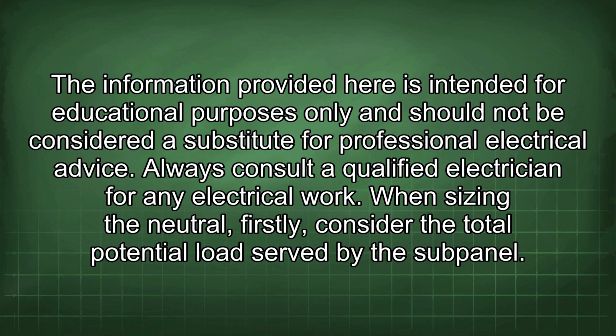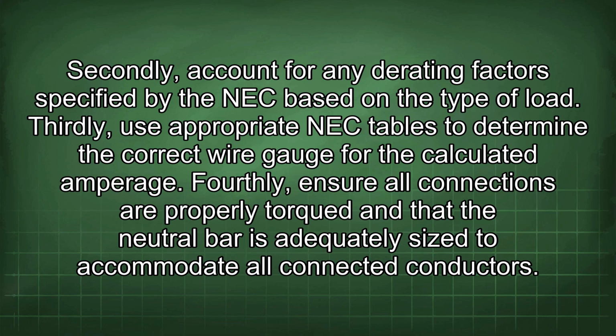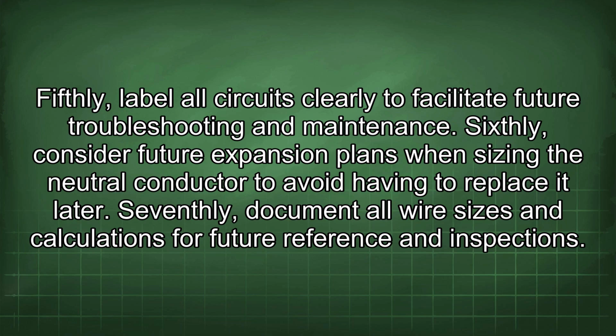When sizing the neutral, firstly, consider the total potential load served by the subpanel. Secondly, account for any derating factors specified by the NEC based on the type of load. Thirdly, use appropriate NEC tables to determine the correct wire gauge for the calculated amperage. Fourthly, ensure all connections are properly torqued and that the neutral bar is adequately sized to accommodate all connected conductors. Fifthly, label all circuits clearly to facilitate future troubleshooting and maintenance. Sixthly, consider future expansion plans when sizing the neutral conductor to avoid having to replace it later. Seventhly, document all wire sizes and calculations for future reference and inspections.